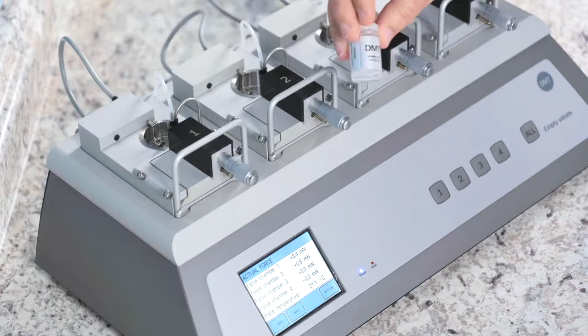If you used hydrophobic reagents in your experiment, you may need to clean it with 96% ethanol to thoroughly clean the chambers. In the event that you used extreme compounds or chemicals, something highly resistant or toxic, you can use 1 molar hydrochloric acid. You can fill the chamber and leave it for up to 1 hour. Make sure in either instance to thoroughly wash the chambers with distilled water. And in the event that you use hydrochloric acid, make sure that all liquid is out of the chambers. And never use bleach in the chambers or the system.